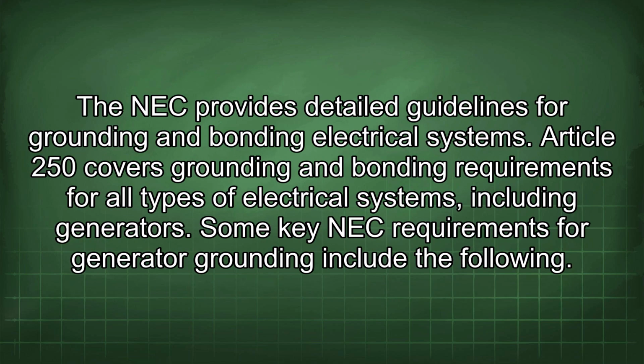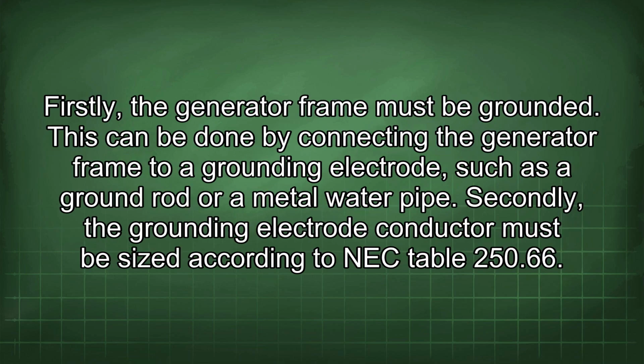The NEC provides detailed guidelines for grounding and bonding electrical systems. Article 250 covers grounding and bonding requirements for all types of electrical systems, including generators. Some key NEC requirements for generator grounding include the following. Firstly, the generator frame must be grounded. This can be done by connecting the generator frame to a grounding electrode, such as a ground rod or a metal water pipe.